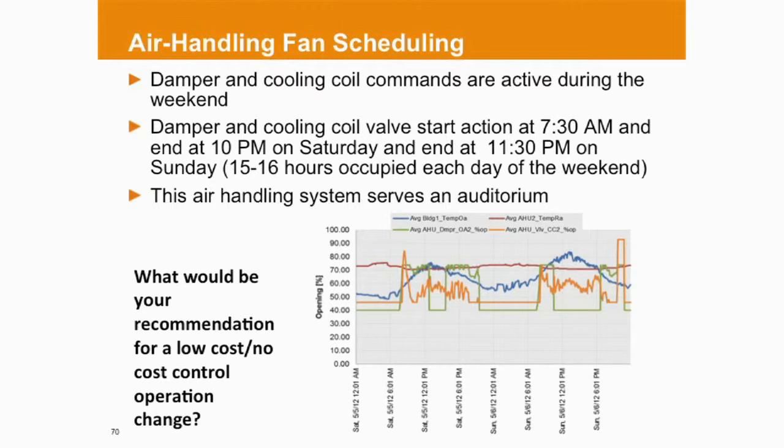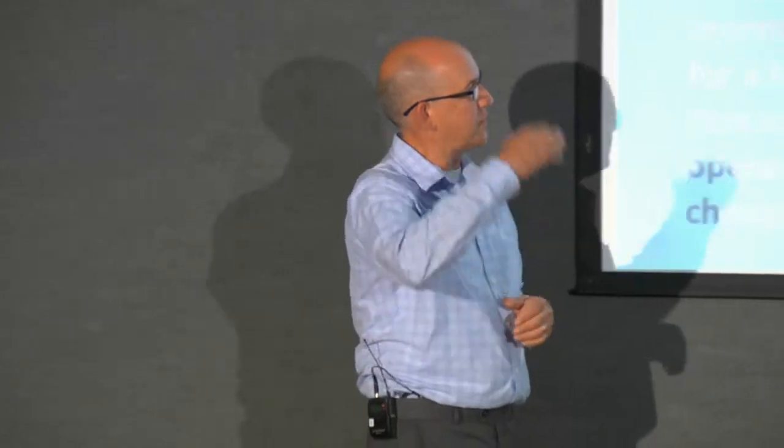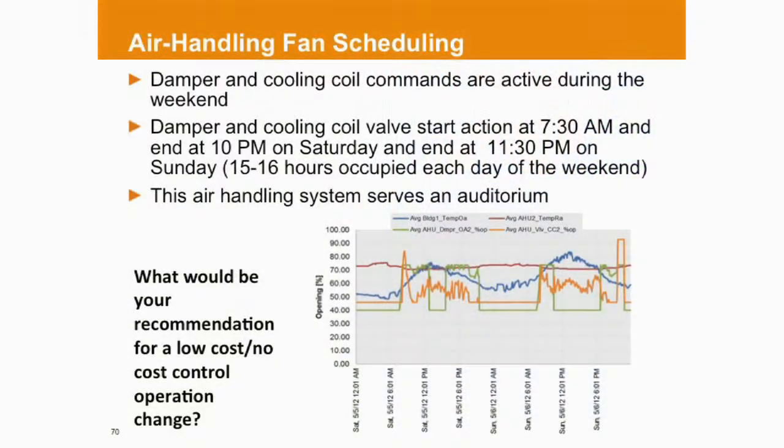We generally emphasize doing integrated economizer, and a lot of people set up their economizers and their cooling valves so that if my economizer is operating, then I'll limit my cooling valve until I get maximum economizer. Some people set up their cooling valves so that once I go to minimum, then I'm going to let my cooling valve go active.